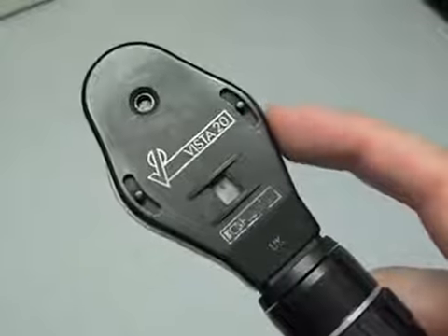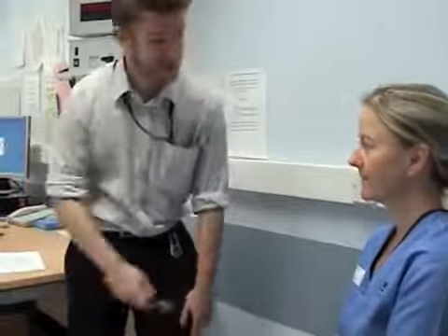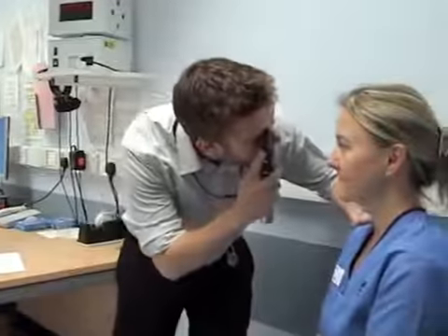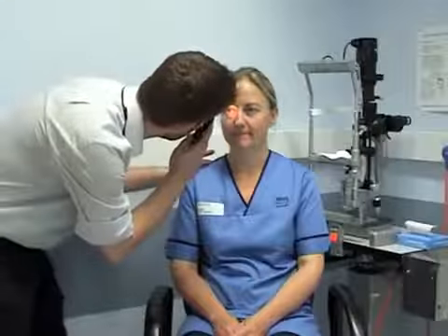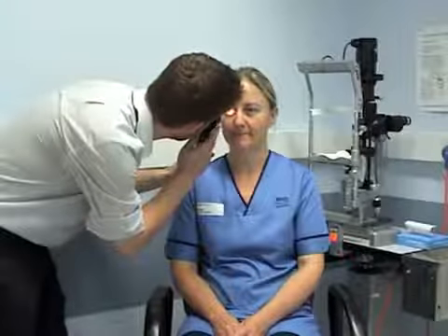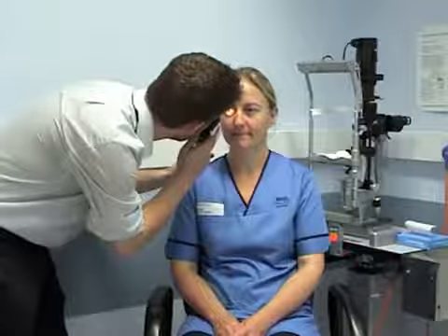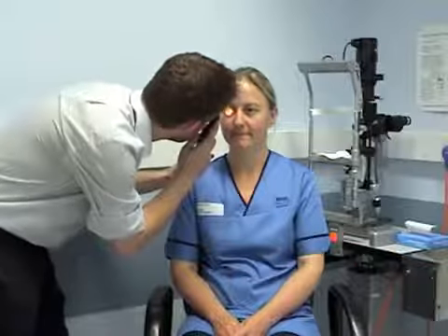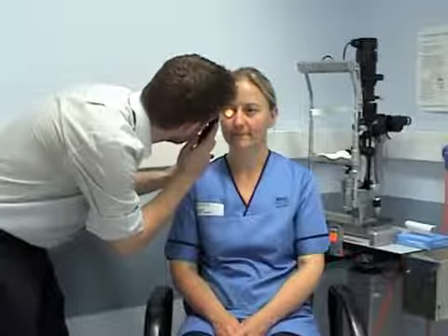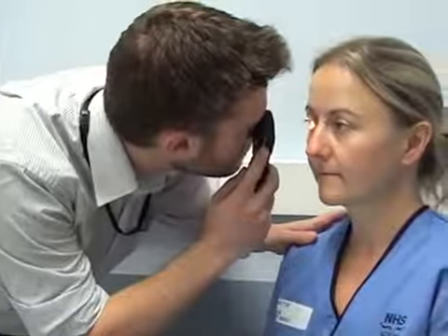Once the red reflex has been tested, a +10 lens is dialed up. The patient must be given clear instructions to look straight ahead or fix on a distant target. Standing at the side of the patient, you come in from a slightly temporal approach. Coming in from an angle of approximately 45 degrees helps one land on the optic disc. With a +10 lens in place, the ophthalmoscope should be focused on the cornea, and this allows examination of the anterior segment of the eye.